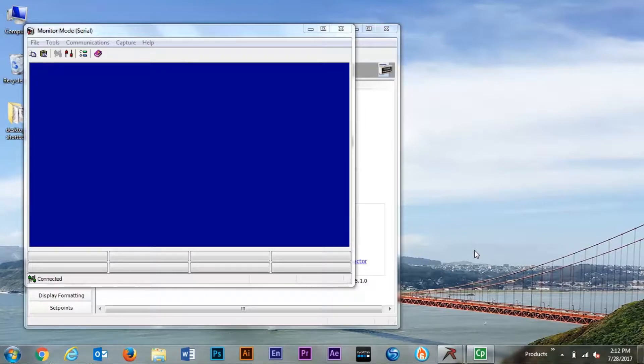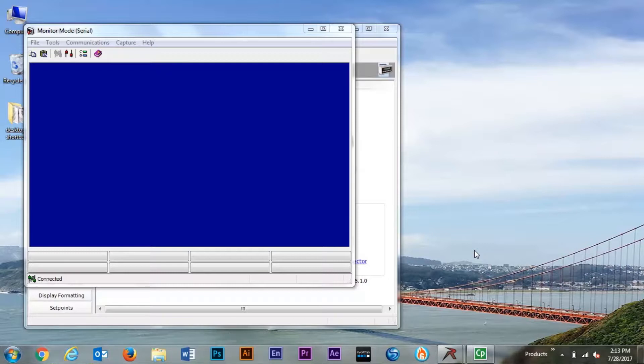Hello and welcome to today's demonstration of troubleshooting serial communications on an 880 indicator. The first thing we're going to do is attempt to send the version command. From sending the version command we should receive a response indicating what version of firmware the indicator is. This is often a standard for troubleshooting.